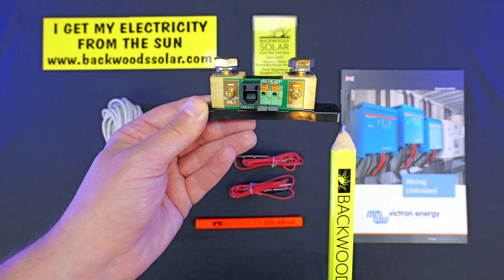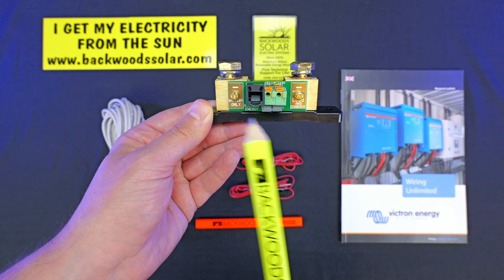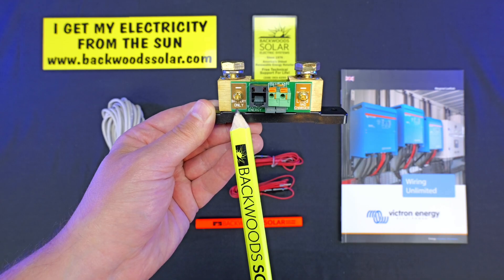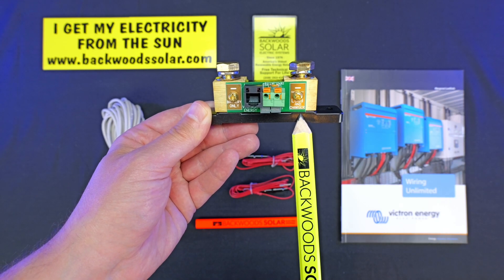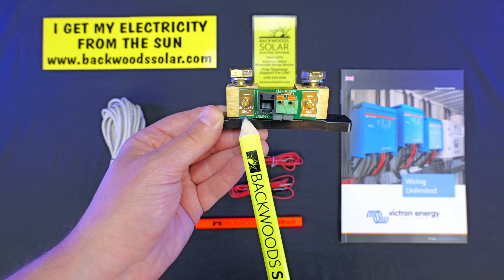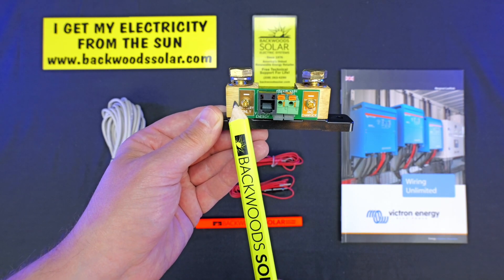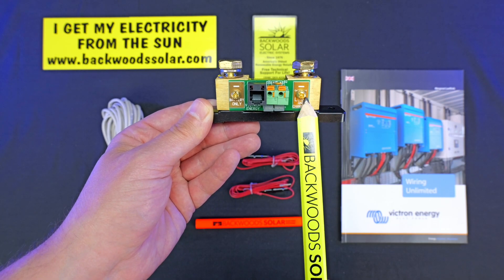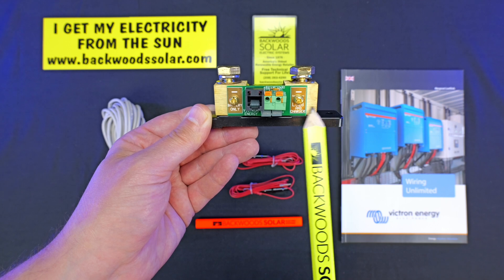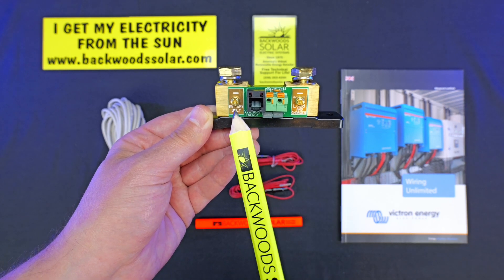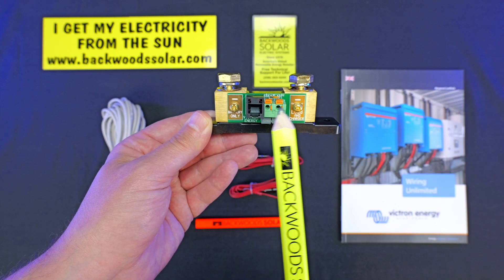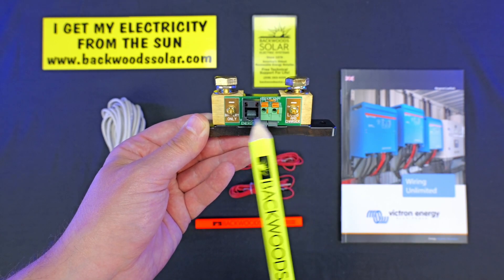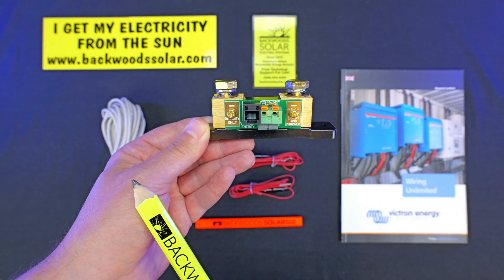It's also very important to take note of the orientation of the shunt. You can see this one here is marked battery only and load and charger only. So it's exceedingly important when you install these that only the battery negative is connected to one side and all of the other system device loads, chargers, etc. are connected to the other. That way, every bit of energy that comes into or comes out of the battery bank is measured through this shunt device.